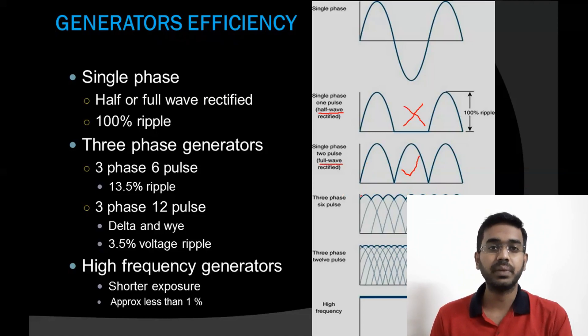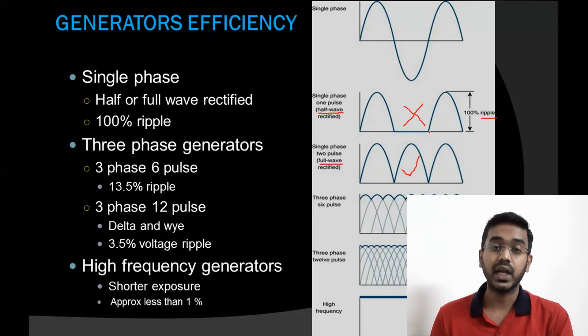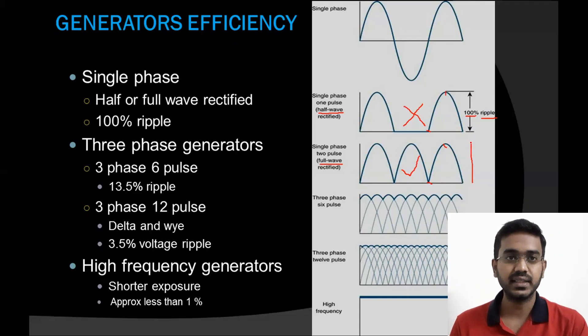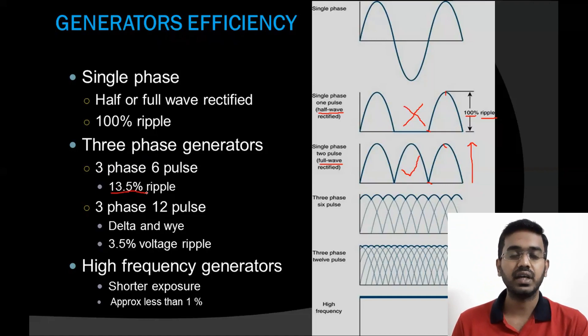One important term is ripple factor — ripple is the fluctuation of voltage. If voltage starts from zero and goes to maximum, it is called 100% ripple factor. In both half and full wave rectification, we have 100% ripple factor. In three-phase six-pulse generators, the ripple will be 13.5%, and in three-phase twelve-pulse generators using the delta and Y method, the ripple will be 3.5%.